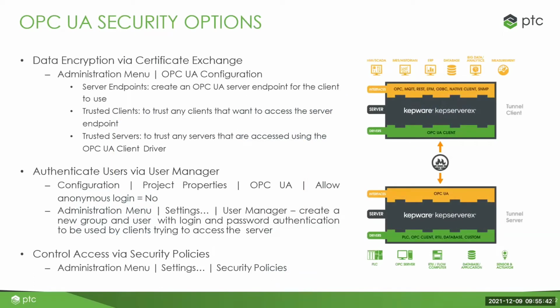So coming back to that, when you have to move data across the wire, what we recommend is that instead of doing a remote OPC DA, anything along that line, do an OPC UA tunnel. The reason we recommend that is, firstly, it's encrypted. If you use the OPC UA tunnel method, you can actually enforce signing and encryption, right? So SHA-256, Basic256Sha256 right now. So that's some of the things that you can do.